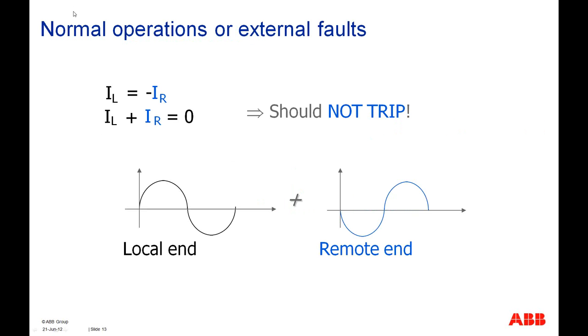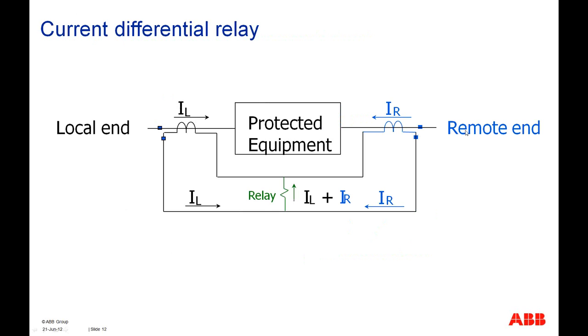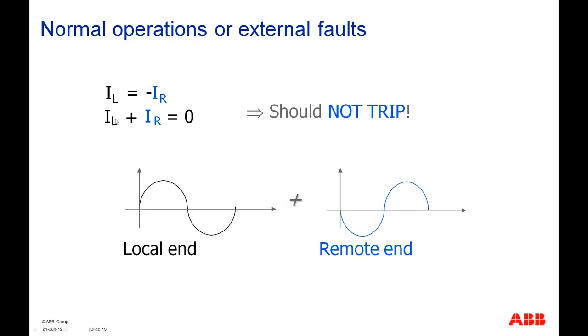So in this case, if the fault is external, somewhere here, then the direction of IL will remain the same, but the direction of IR will reverse, 180 degrees opposite. So in that case, IL will be equal to minus IR. Therefore, if we add up these two currents, the resultant would be 0, and there will be no trip. This is the local current, and the remote current is 180 degrees opposite. If we add these two diagrams, we get a 0 differential current. So there will be no trip.